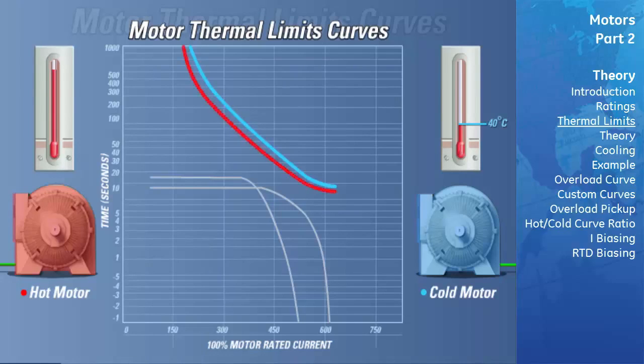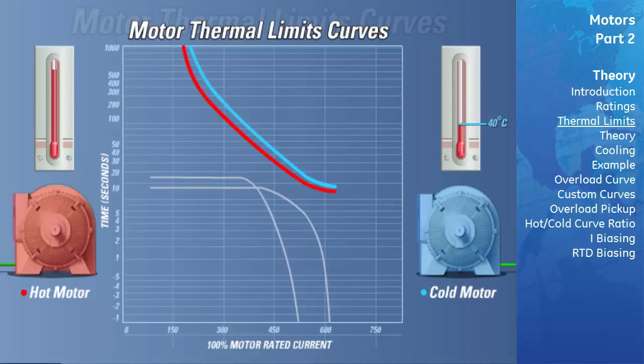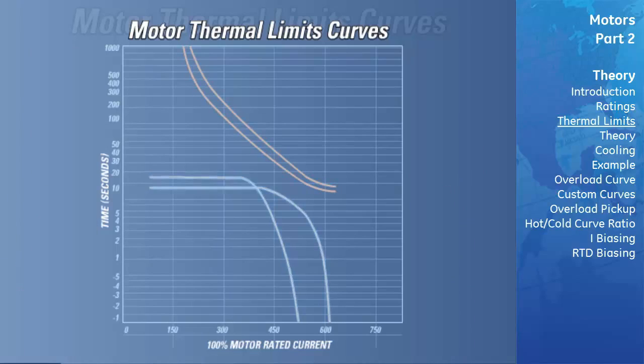Likewise, the hot thermal limit curve indicates the amount of overload current the motor can withstand before damage occurs when the motor is hot — meaning it has been running at rated full load current for an amount of time such that the temperature of the motor has risen to its rated temperature above the ambient temperature of 40 degrees Celsius. The acceleration curves are an indication of the amount of current and associated time for the motor to accelerate from a stop condition to a normal running condition.